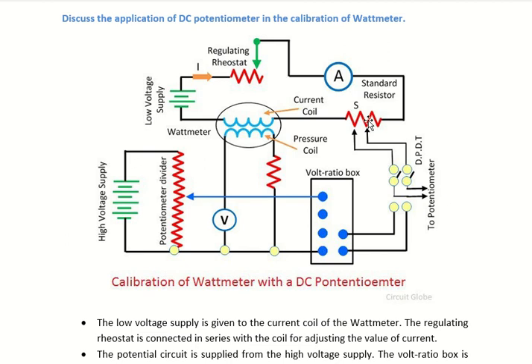From this voltage you can find current by Vs by S, as in calibration of ammeter. So you calculate current and voltage using the potentiometer, multiply current into voltage to get the power, the wattmeter power. Check whether that power calculated from the potentiometer is the same as the wattmeter reading. If they are the same, the wattmeter is calibrated; otherwise it shows an error.